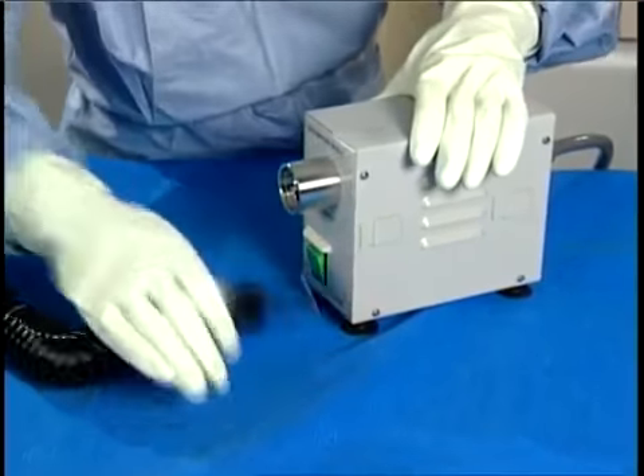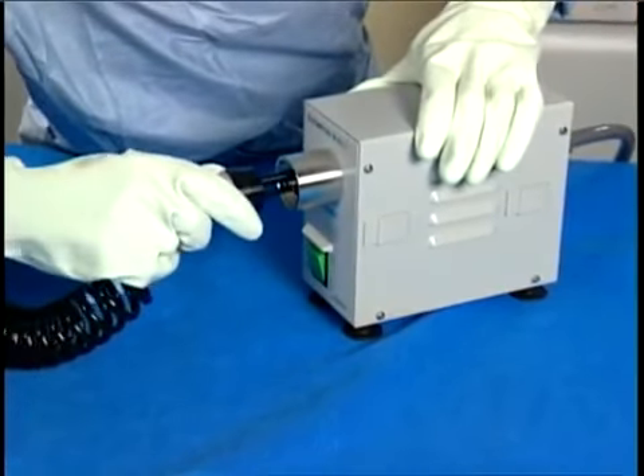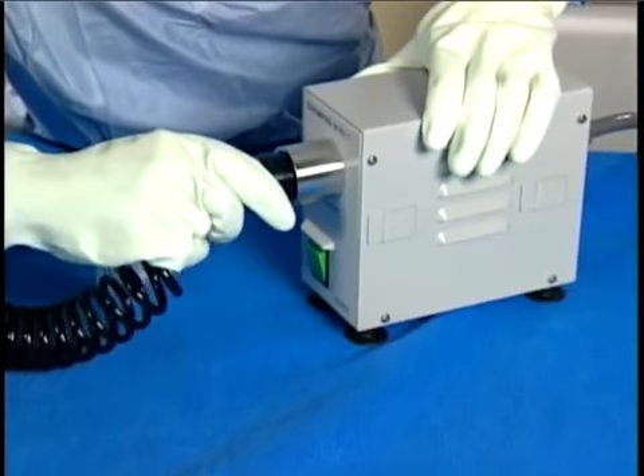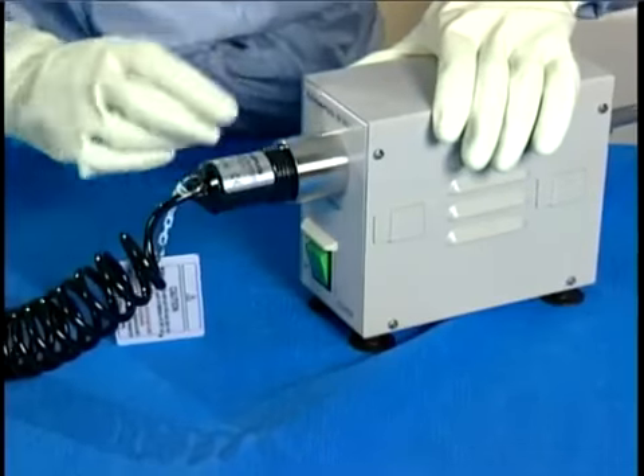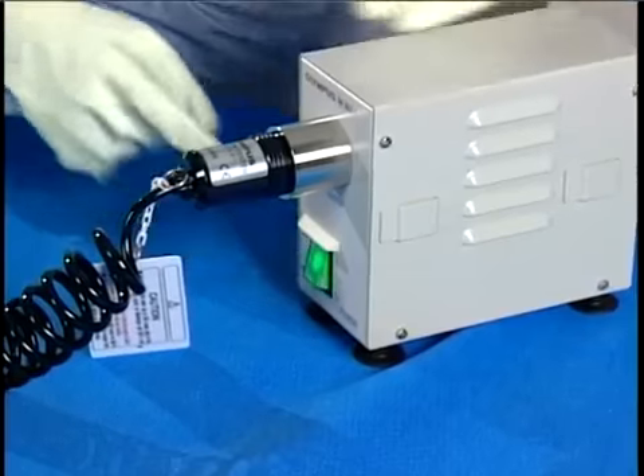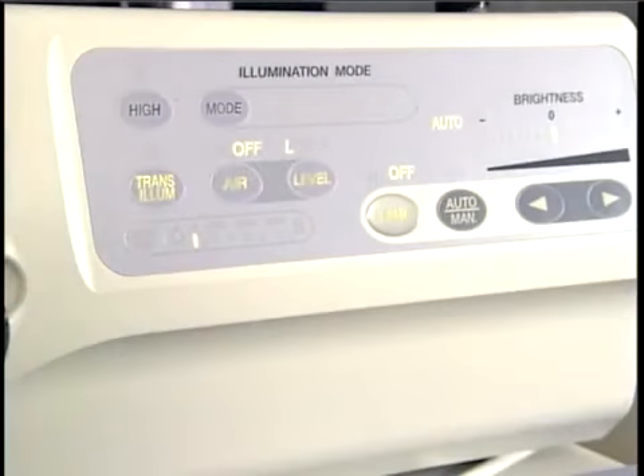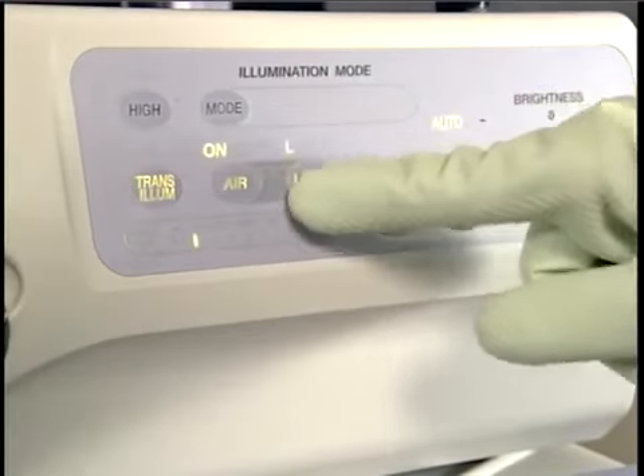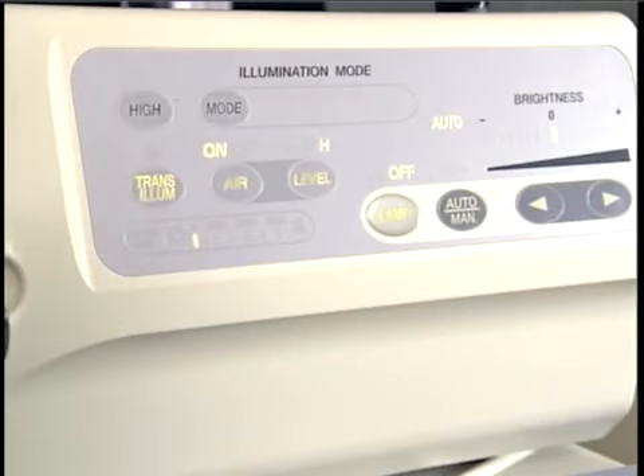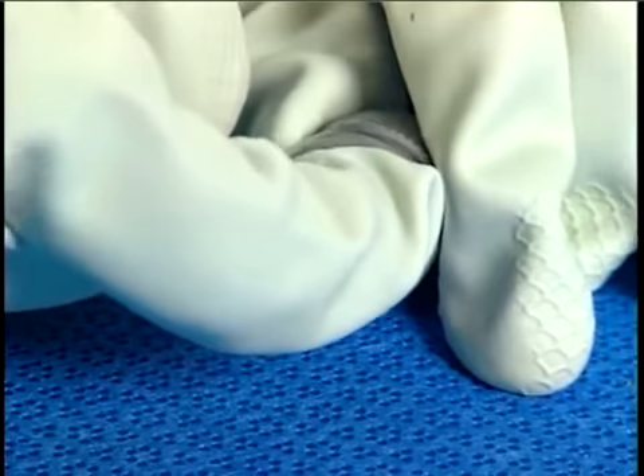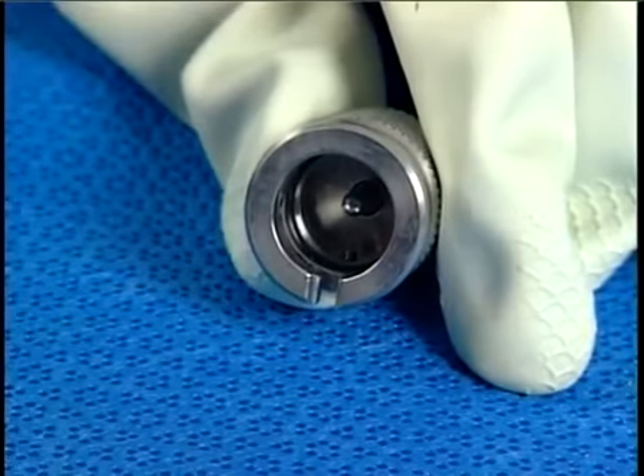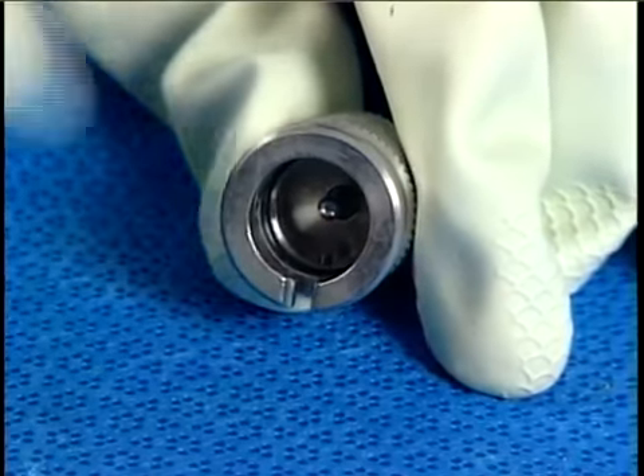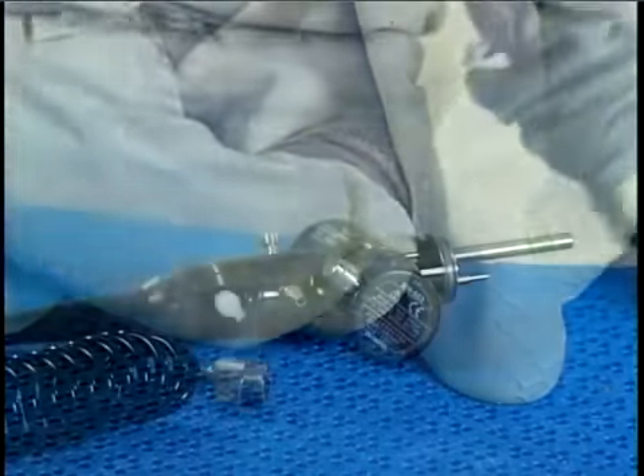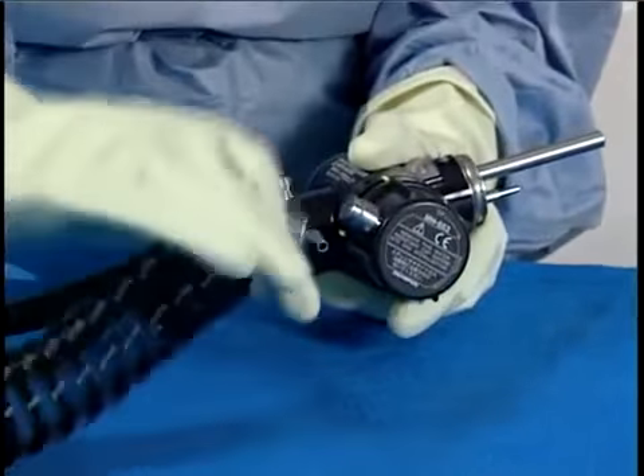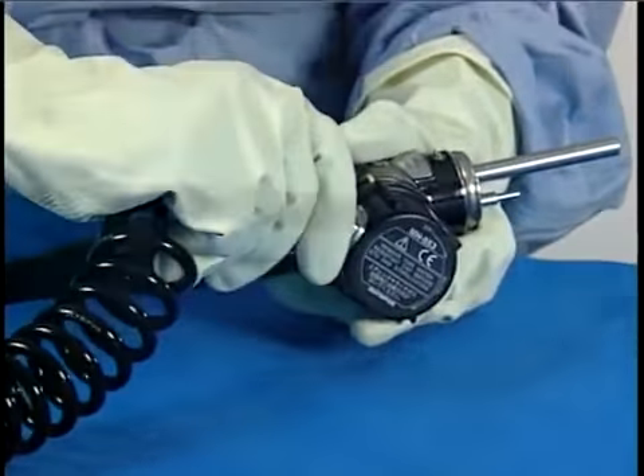Attach the leakage tester to the MU1 maintenance unit or to an Olympus light source. Turn on the air supply. If you are using a light source, be sure to set the airflow rate to its maximum setting. Depress the pin inside the connector and confirm that air comes out of the cap. Now, attach the leakage tester to the endoscope.